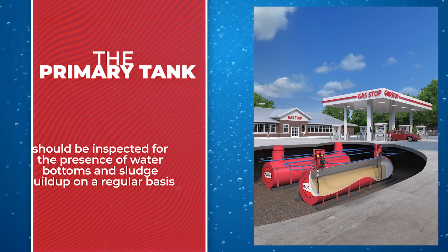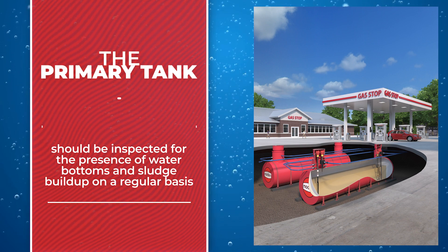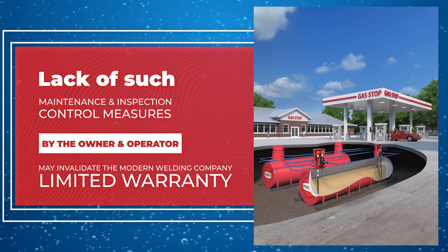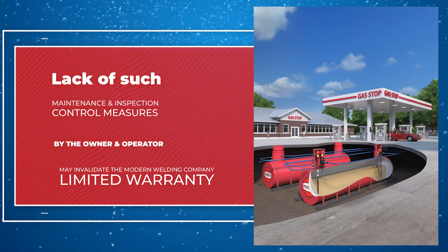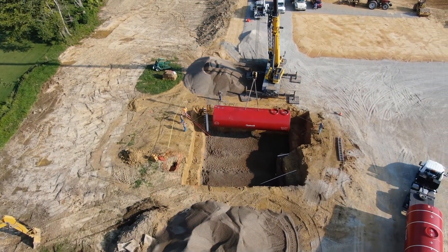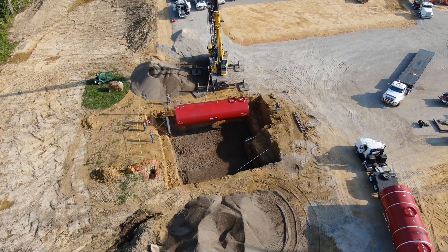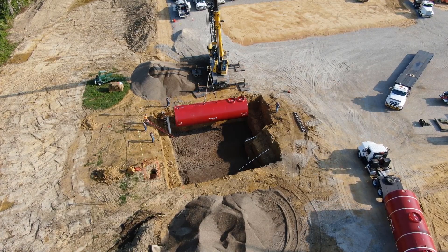The primary tank should be inspected for the presence of water bottoms and sludge buildup on a regular basis. Lack of such maintenance and inspection control measures by the owner and operator may invalidate the Modern Welding Company limited warranty. Thank you for choosing Modern Welding Company for all of your fuel storage needs. Please do not hesitate to reach out to one of our sales managers with any questions regarding the installation of your Glasteel II underground fuel storage tank.